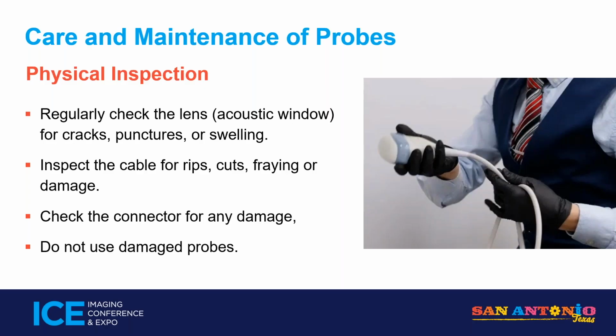So whenever you're in front of an ultrasound system, take the 2 minutes, 5 minutes, it depends how many probes they have, but at least the ones on the system. If they have them in a cabinet put away, I maybe won't see those, but the ones on the system, you can take a quick look at and see some damage and correct it right away. So anytime I'm in front of a system, I take a look at the probes. They are high failure items. They're used every day with the ultrasound. So take a look at them.